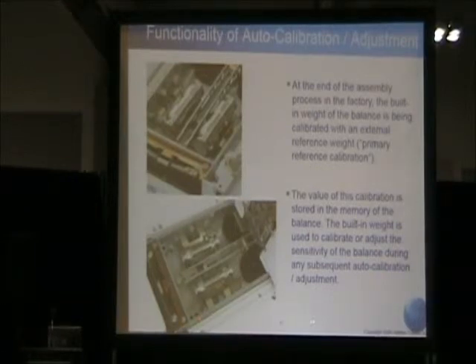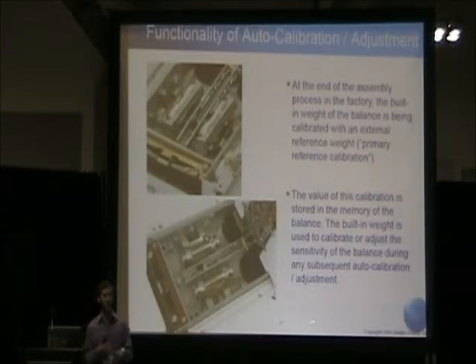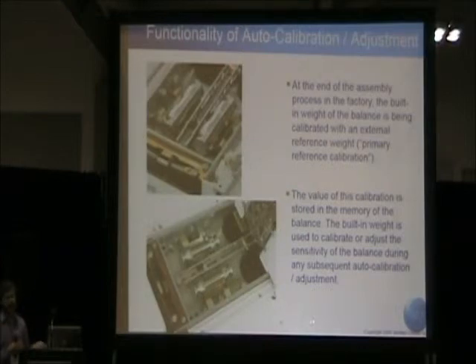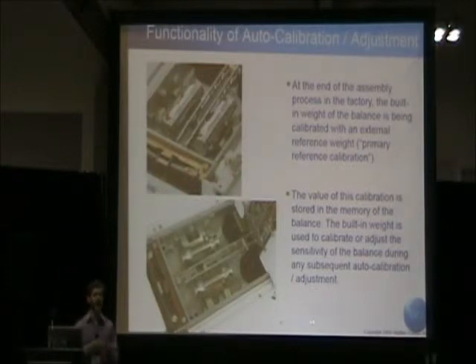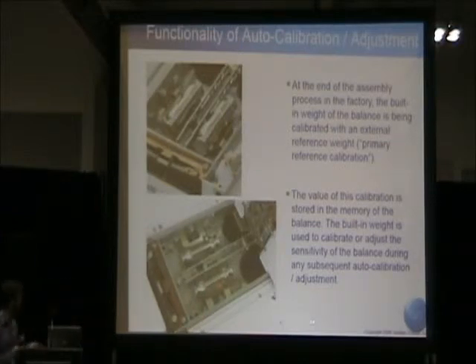These are 2 pictures of a Mettler-Toledo balance and what the internal calibration weights look like. At the end of the production of these instruments, these weights, which have a known value, are placed inside your instrument. That known weight is then inputted into your microprocessor. And whenever that internal adjustment kicks in, the balance is adjusting that microprocessor value to these two internal weights. Now, these are basically dummy steel masses inside your instrument, and over time they can oxidize and change the actual weight themselves. So it's important to have technicians who have the capability to adjust these. Whatever instrumentation you're using, the manufacturer will typically be able to go internally into your instruments and recalibrate those calibration weights. As an example, if a Mettler-Toledo technician comes in to calibrate a Mettler-Toledo balance, he will test these internal weights to see if they're within tolerance, and if they're not, he'll be able to adjust them accordingly.